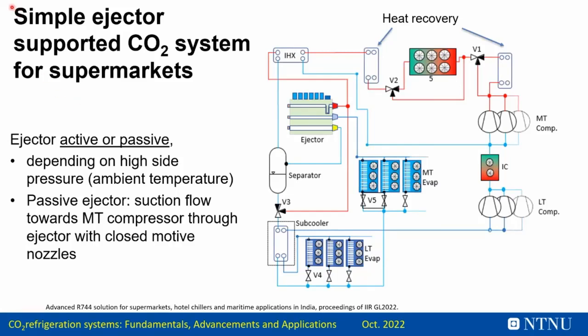What we have lately developed and proposed for an installation in India is a simpler ejector system where we can support the CO2 with an ejector in an active and passive mode. It depends on the high temperature on the heat rejection device whether the ejector is passive or active. When it is active, it sucks all the vapor from the MT evaporators and pushes it into the separator, and the separator pressure is maintained by the MT compressors.